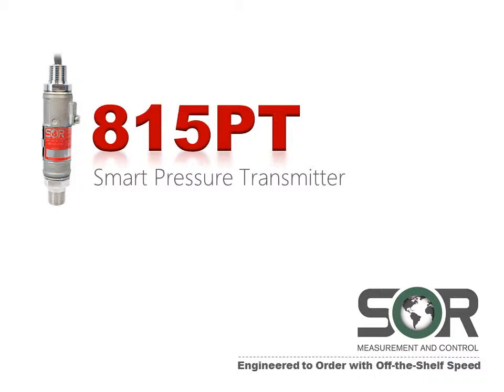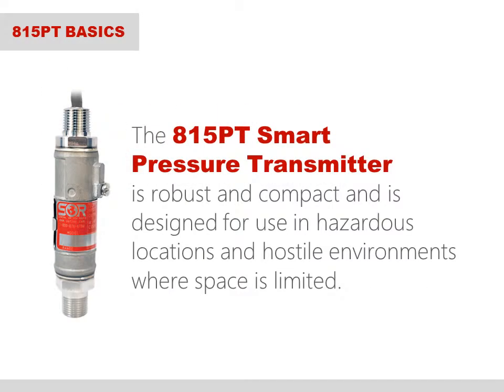In this presentation, I will review the form, fit, function, features, and benefits of the 815PT Smart Pressure Transmitter. The 815PT is an explosion-proof pressure transmitter designed for use in hazardous locations and hostile environments. It has a compact footprint that is less than 6.1 inches long and less than 1.4 inches wide. This small footprint makes it ideally suited for installation in tight spaces.